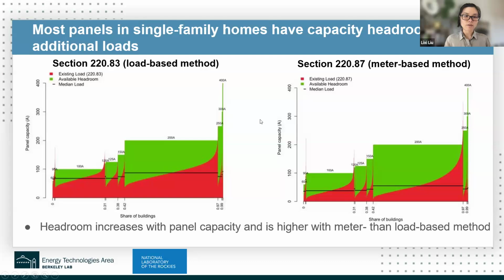As Sean presented earlier, we calculated headroom two ways. The first is the load-based method on the left, which estimates total connected load by summing equipment ratings together and then applying demand factors. The second is the meter-based method on the right, where we use simulated electricity data from ResStock instead of meter data to estimate peak demand. You can see that the meter-based approach tends to show more headroom because the load-based demand factors are generally more conservative in estimating coincidence of usage than real-world usage.